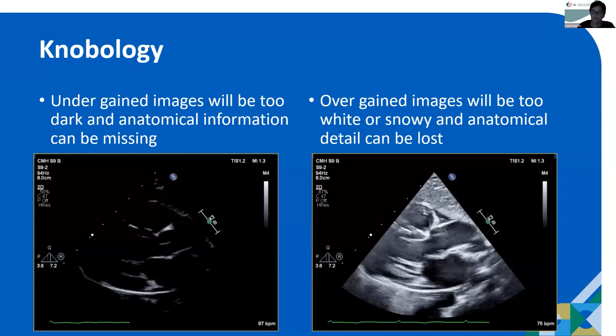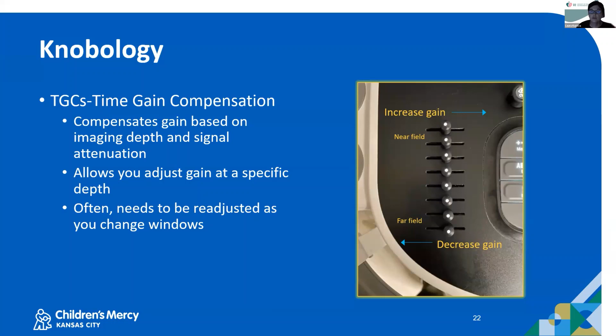So we've hit our iScan button, we adjusted our 2D gain. Now we can look at our TGCs if we need to make some finer adjustments. These are the little slide pots on the left side of the control panel, and they can adjust your gain based on your depth and signal attenuation. Often you are going to need to decrease your gain in the far field, so you'll slide the little slides to the left. You can increase your gain in other areas if you need. And remember that this is something you are going to probably adjust in every window.